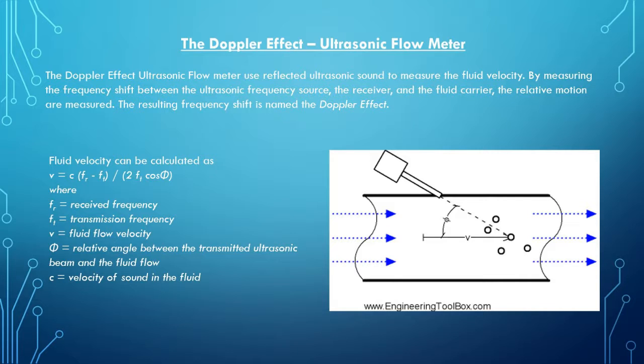Ultrasonic flow meters use reflected ultrasonic sound to measure the fluid velocity. By measuring the frequency shift between the ultrasonic frequency source, the receiver, and the fluid carrier, the relative motion is measured. The resulting frequency shift is named the Doppler effect. This can be used to calculate the fluid velocity by using the formula on the screen and in your handout.